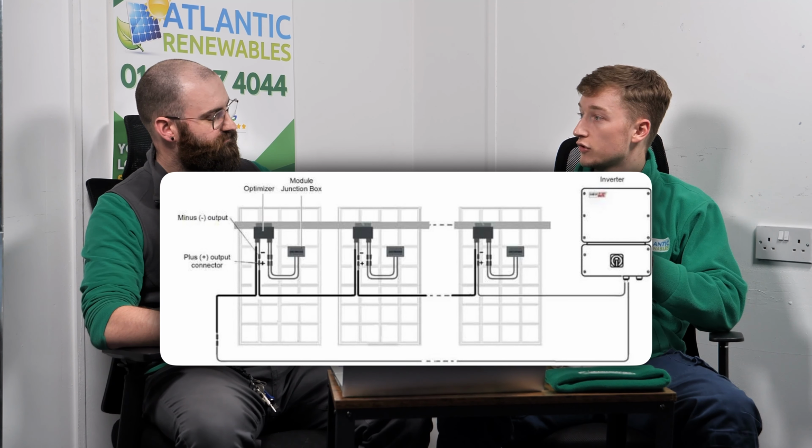Yeah, so as you say, they're not typically installed with the basic systems. It's when there are shading problems from chimneys, trees, flues, other neighbouring buildings and things like that, which isn't for everybody. But when we do see something that could cast a shadow in a specific area of the solar array, we try and take action with either optimizers with SolarEdge or Tigo. SolarEdge is typically the full optimized system, so every single panel on that system will have an optimizer, and you get the central inverter with SolarEdge as well.